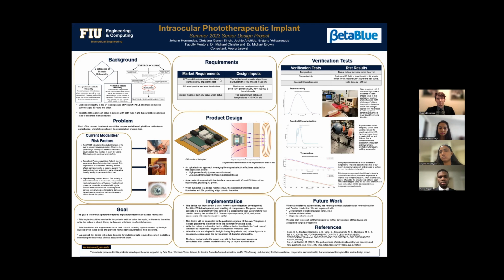Lastly, for safety's sake, we decided to make a market requirement that the implant must not burn any tissue when active. In order to meet this market requirement, we created a design input that the implant must not reach temperatures above 38.5 in situ, which is 1.5 degrees Celsius above body temperature at homeostasis.